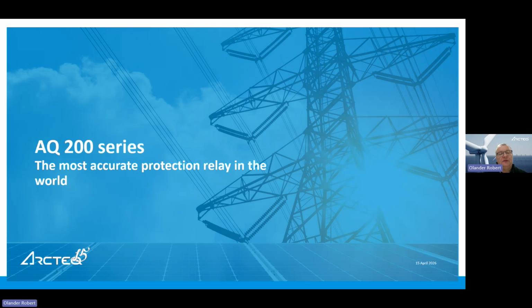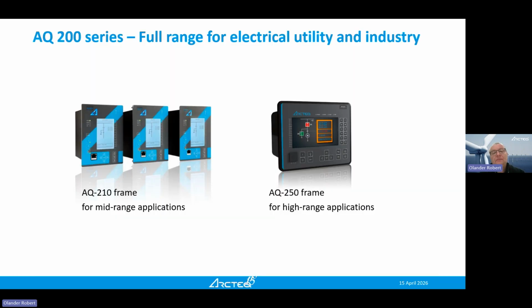Okay, AQ200 series. So the most accurate protection relay in the world. I will explain to you what I mean by that. So in the 200 series, we have 2 different frames. We have the 210 frame and we have the 250 frame. Basically, the biggest difference is that in the 210 frame, we have 6 option card slots, and in the 250 frame, we have 14 option card slots. So basically, it means that you can expand the 250 much more. Protection-wise, they are quite identical.